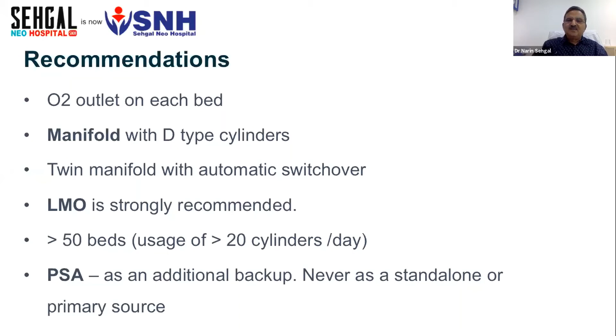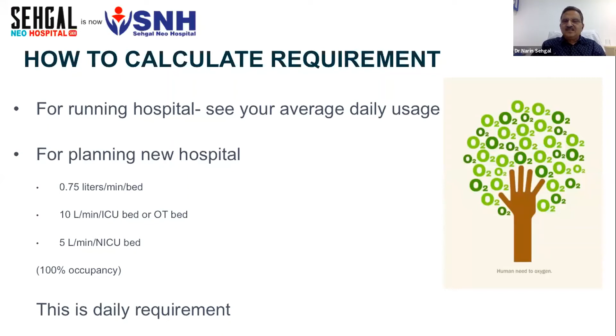Now, another thing which comes up, which I think Dr. Lallu also defined in the beginning, is how to calculate the requirement. It's the same parameters she advised: whatever you normally use in normal circumstances, or if you are planning a new one, then 0.75 liters per minute per bed, or 10 liters per minute per ICU bed or critical area, or 5 liters per minute for a NICU bed. Once you calculate your daily requirement, my recommendation is that right in the beginning you should plan and have a supply of approximately 3 to 4 days. So 3 times is what I recommend for my colleagues with smaller hospitals. They must plan to remain safe from the eventuality which we faced this time. Automate as much as possible.